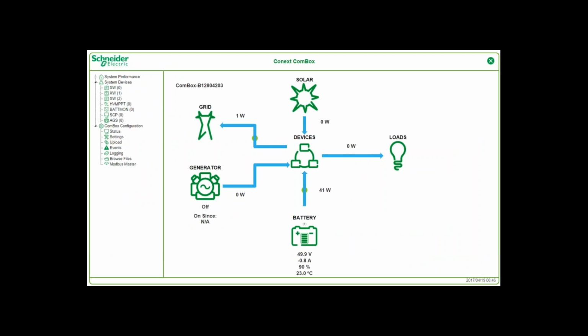Once logged in, the system status page appears. Here we see mapping of the devices and direction of power flow in watts is displayed in real time. Note the battery voltage, amperage, state of charge percentage, and temperature that is reported by the Conext battery monitor. On the left side of the web page, you see all the Xanbus devices in the network. So you'll note that this is a triple XW system. We've got one high voltage MPPT controller, a battery monitor, system control panel, and an automatic generator start.